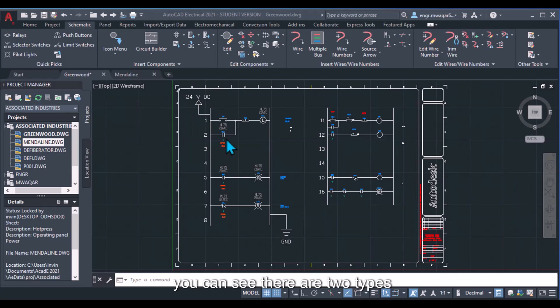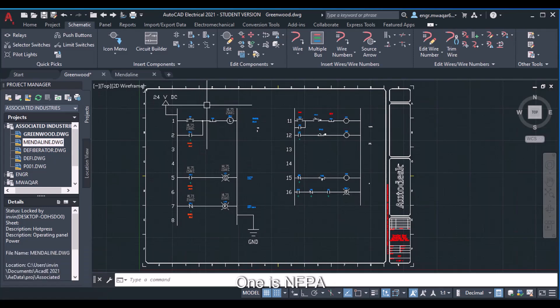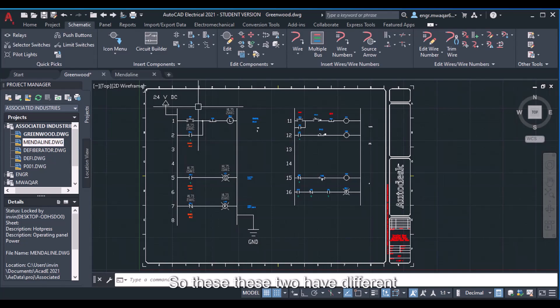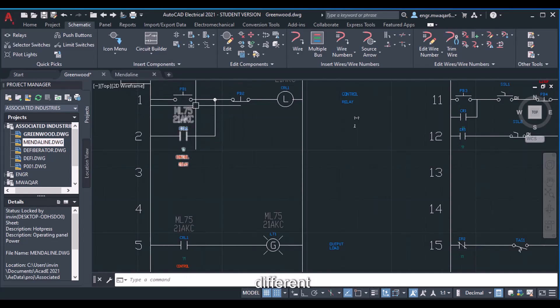In the open drawing you can see there are two circuits in a single drawing. You will find two forms of symbols: one is NFPA and JIC symbols, which are imperial and in inches, while the second one is IEC symbols, which are in millimeters. These two have different forms of symbols for the same components — for example, a push button symbol looks different in NFPA versus IEC.